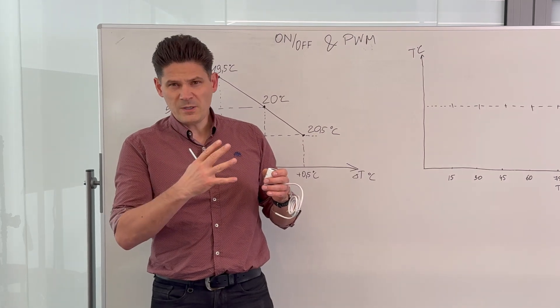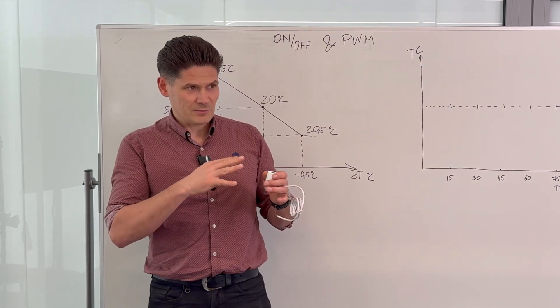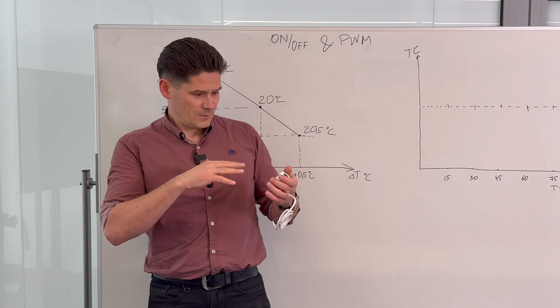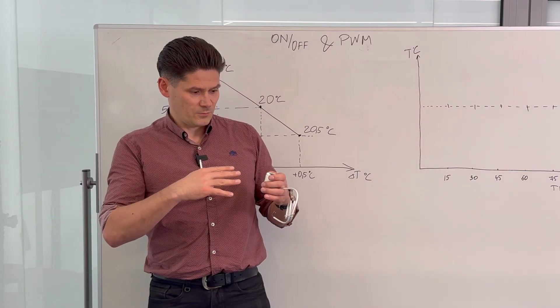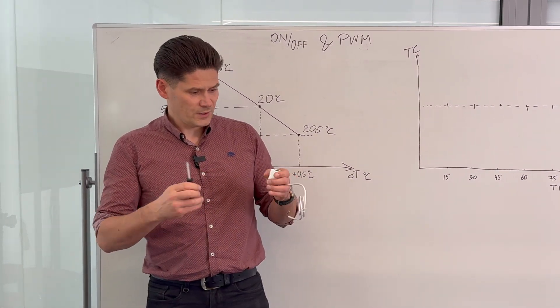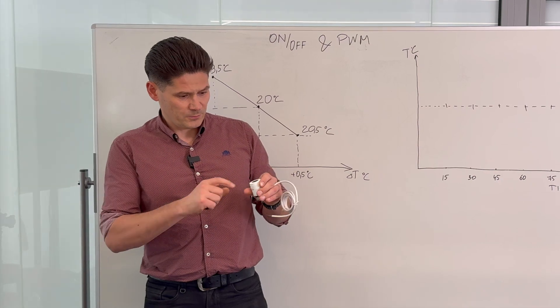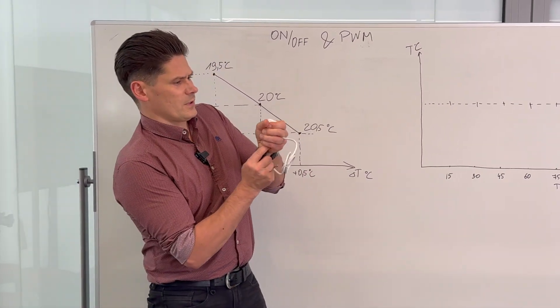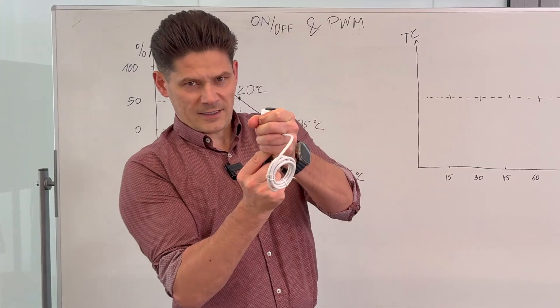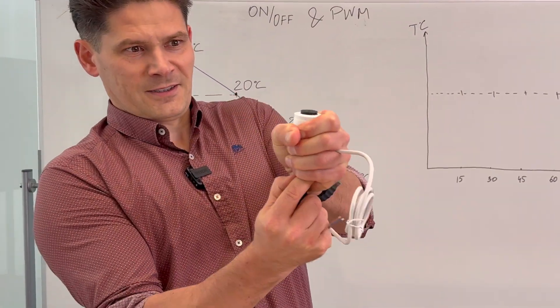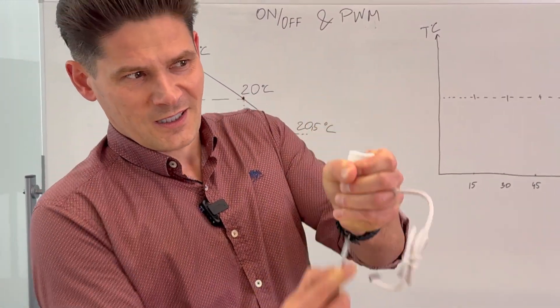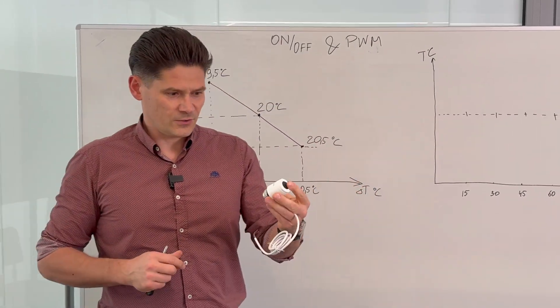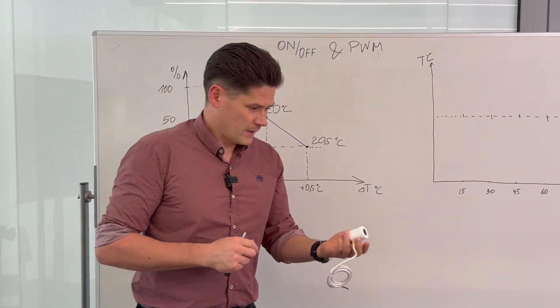These are wax-filled actuators and they usually open in around five minutes - sometimes less, sometimes longer, depending on the producer. I can push and open it - it looks like this. The indicator shows it is open; if the indicator is down, the actuator is closed.